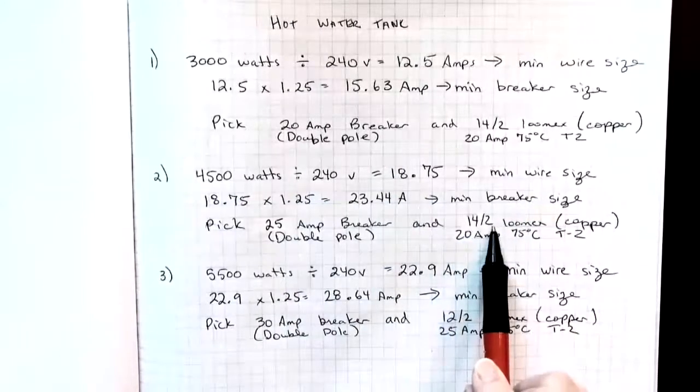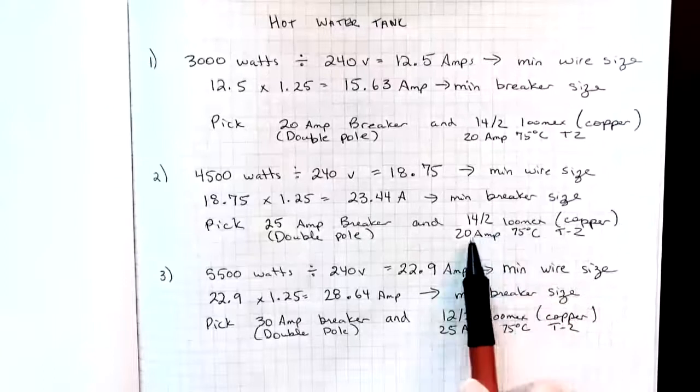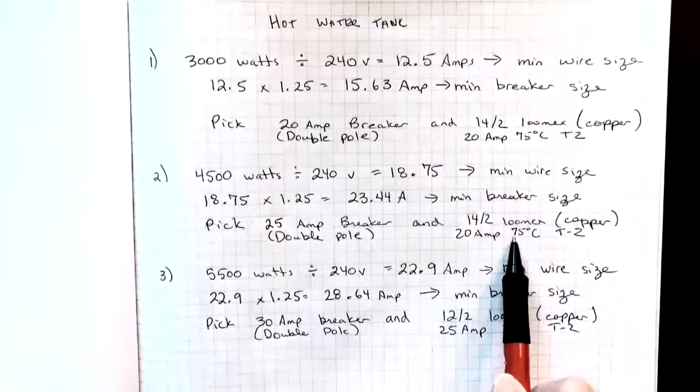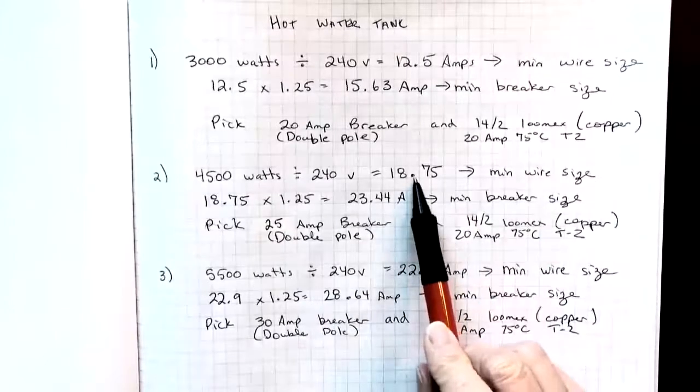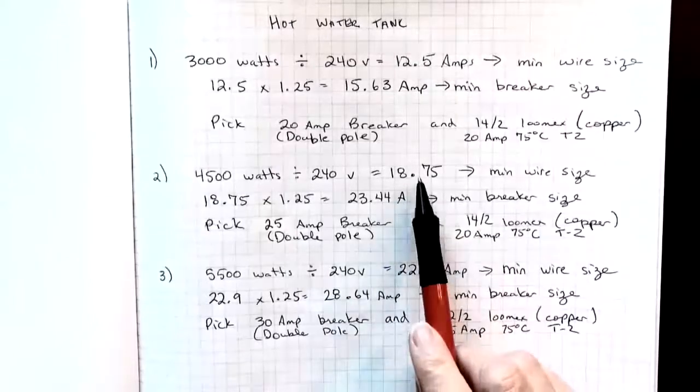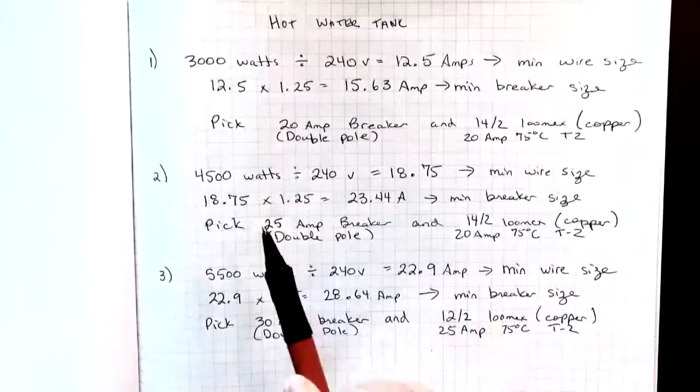Down here I picked the 14/2 Loomex copper because in table two, it tells us again that it's 20 amps in the 75 degree column which is enough to cover our load. Remember our ampacity of the wire always has to be at least as big as the load.